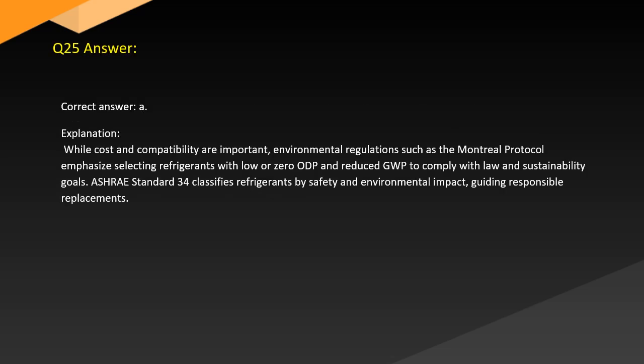Answer. Correct answer: A. Explanation. While cost and compatibility are important, environmental regulations such as the Montreal Protocol emphasize selecting refrigerants with low or zero ODP and GWP to comply with law and sustainability goals. The ASHRAE Standard 34 classifies refrigerants by safety and environmental impact, guiding responsible replacements.